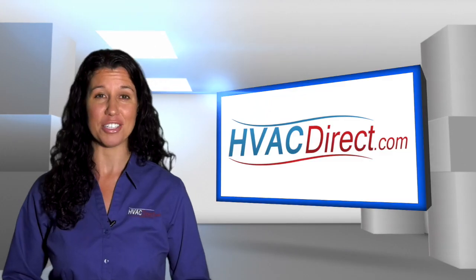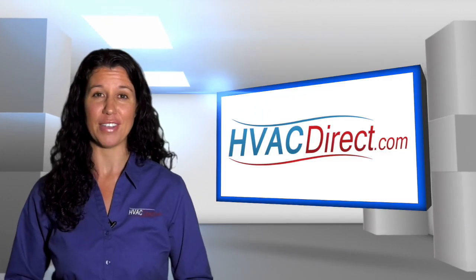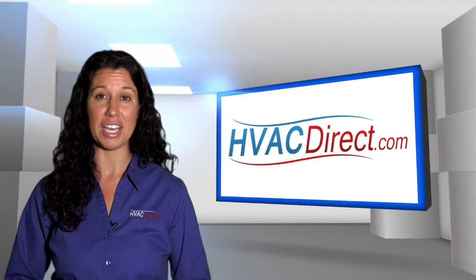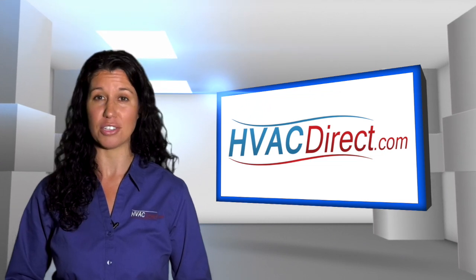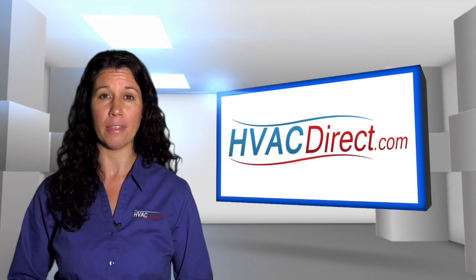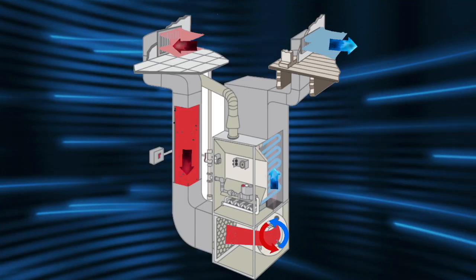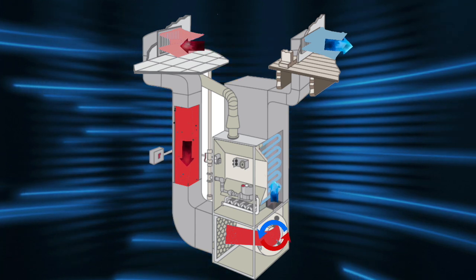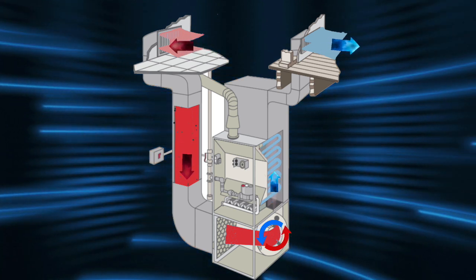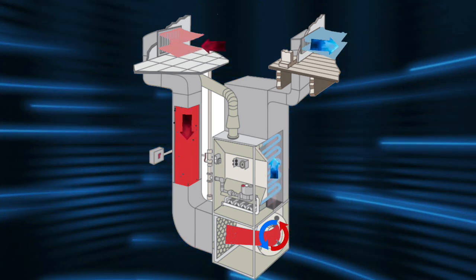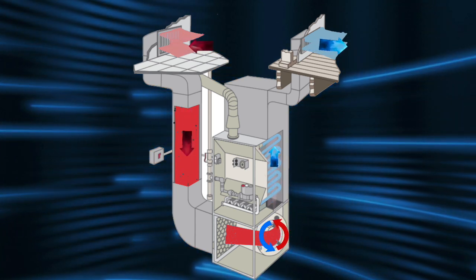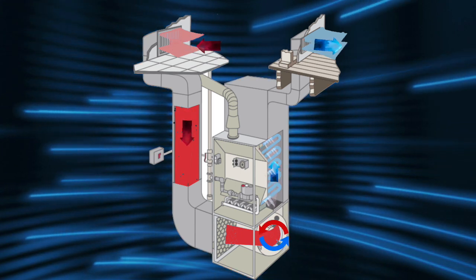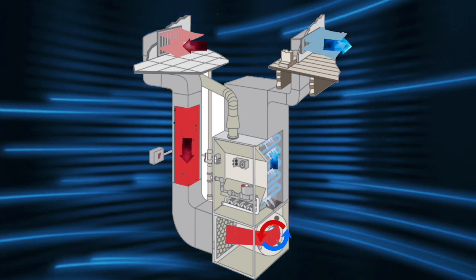Higher pressure on the furnace fan may cause less than 400 CFM per ton to flow across your coil. This may be a result of dirty filters or improperly sized ductwork, and will cause your indoor evaporator coil temperature to approach freezing.